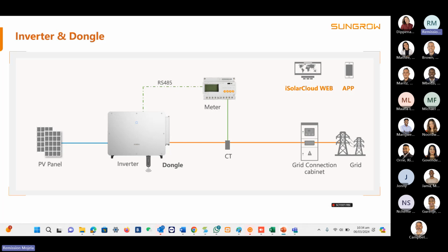It will be meter going directly to the bus of the inverter, and then via RS485 and the dongle plugged in on COM3 of that particular inverter, and the CT sitting in the main incomer so that the CTs can read the power that's actually coming from the grid. And then you do your setup, you do your commissioning, and that will work.